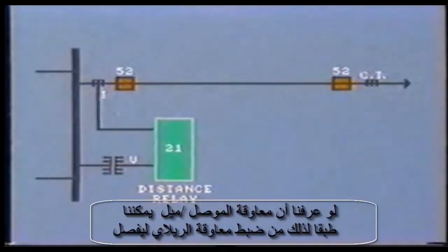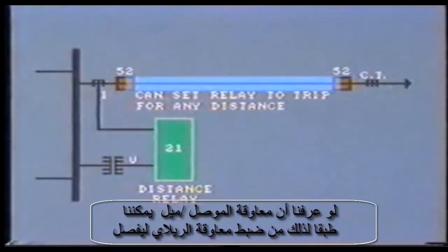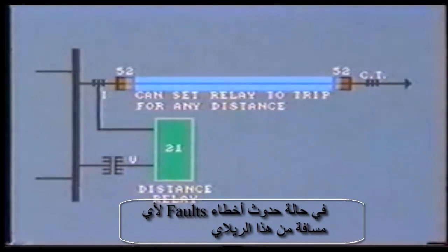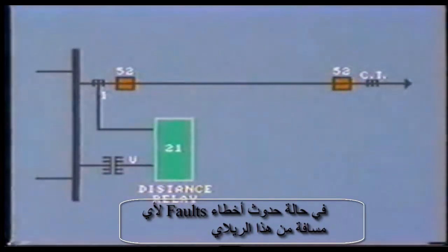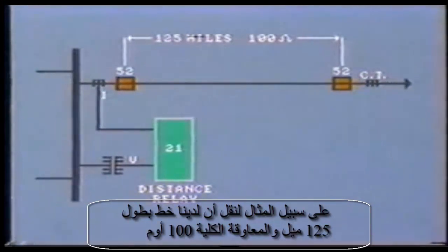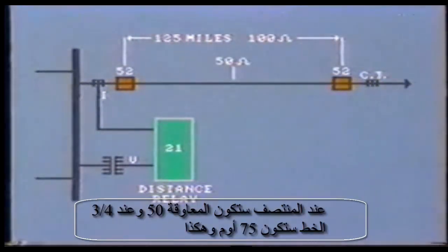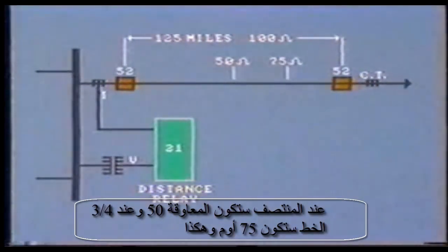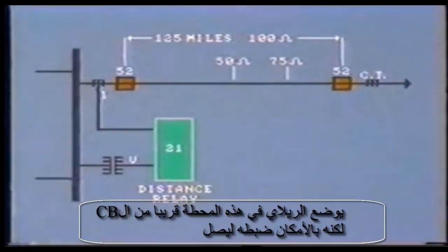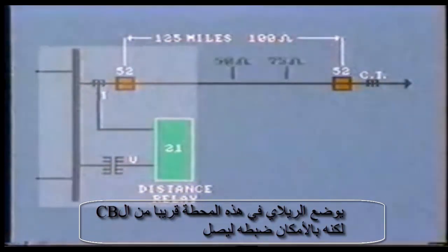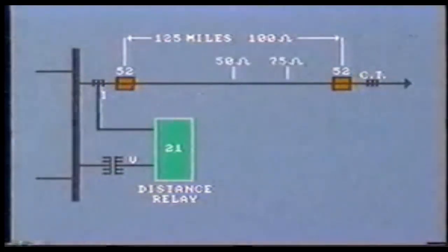If we know the impedance per mile of the line conductors, we can set the impedance relay to trip for faults within any particular distance from the relay. For example, let's say this line is 125 miles long and the total impedance is 100 ohms. At the halfway point the impedance will be 50 ohms, at three-quarter length 75 ohms, and so on. The relay will be installed at this substation, close to the breaker, but it can be adjusted to reach out as far along the line as we wish.